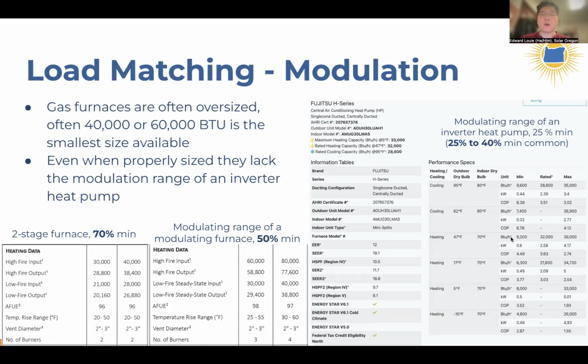So, a really low amount of heat, so that on a mild day when it's sunny and you get that additional heat gain through your windows, your house might only need a tiny bit of heat output to stay comfortable. And a modulating or inverter driven heat pump can do that, resulting in long run times to, again, keep those interior surfaces warm. And that large modulation is much greater than the modulating range of even modulating furnaces or two-stage furnaces.